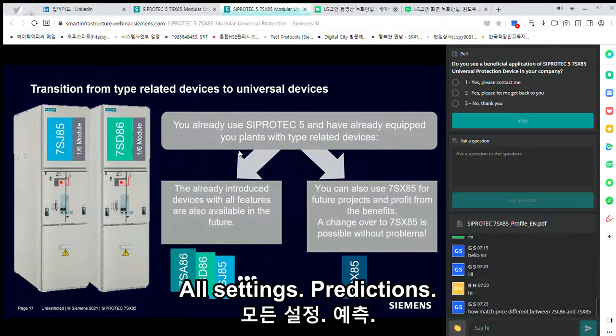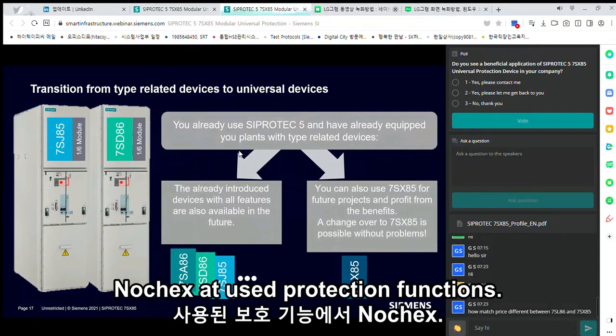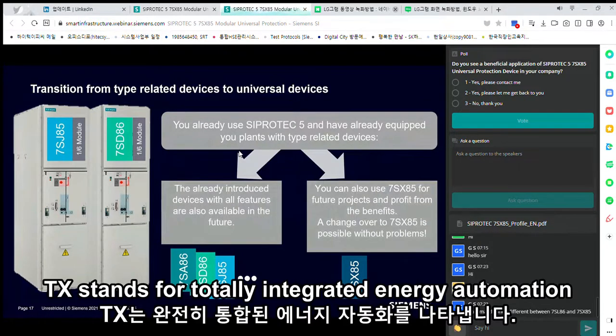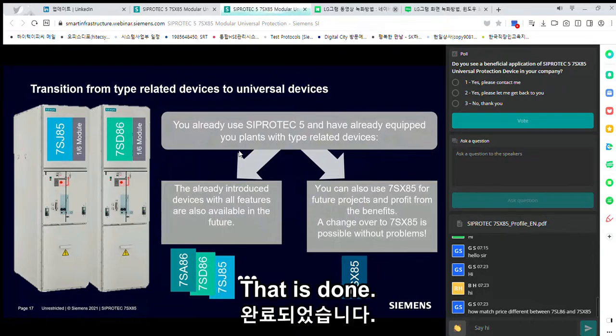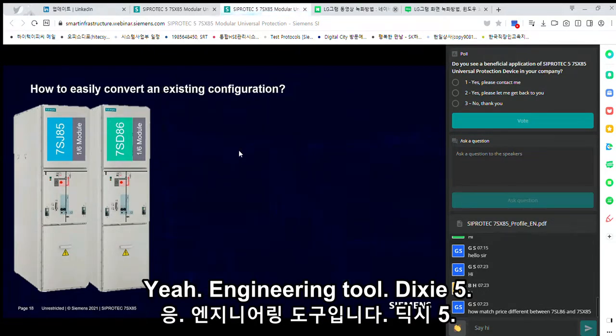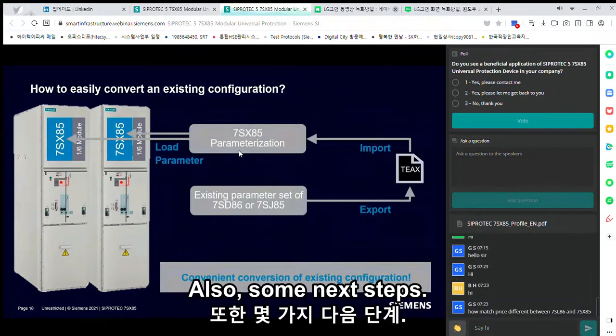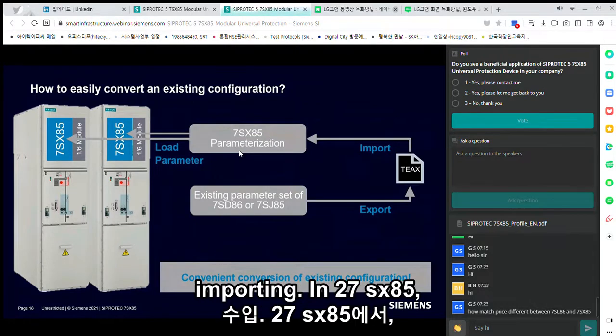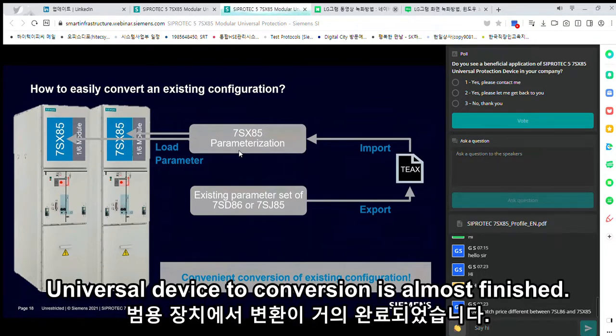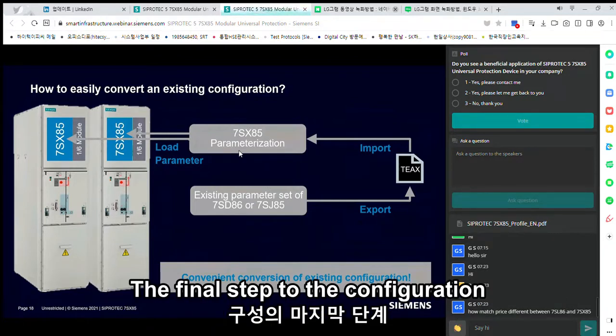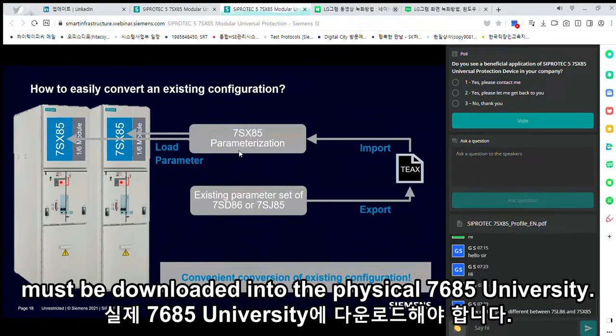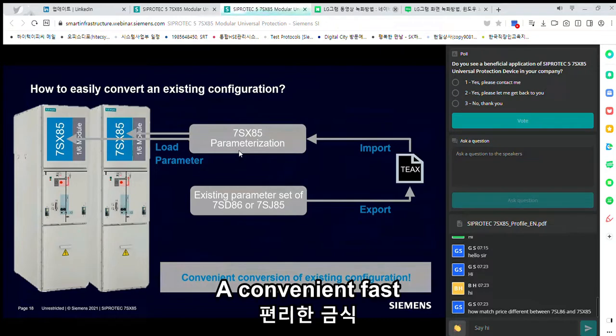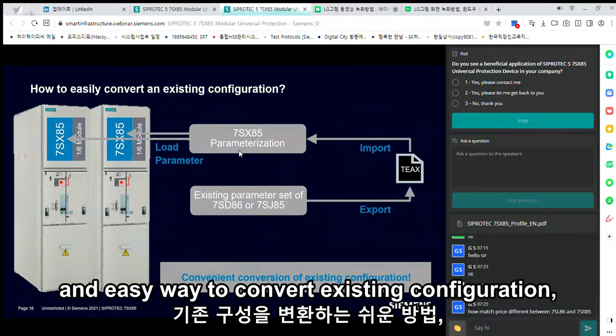All settings, connections, logics and used protection functions can be exported into a TEAX file. TEAX stands for Totally Integrated Energy Automation Exchange format. That is done via the engineering tool DIGSI 5, as also the next steps I will explain. By importing the TEAX file into the 7SX85 universal device, the conversion is almost finished. In a final step, the configuration must be downloaded into the physical 7SX85 universal device. A convenient, fast, and easy way to convert an existing configuration, right?